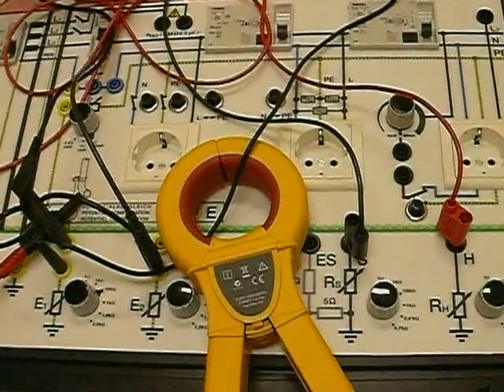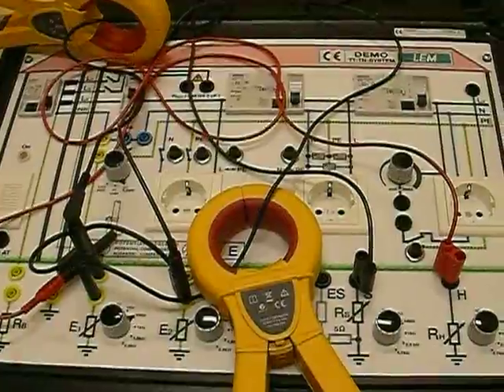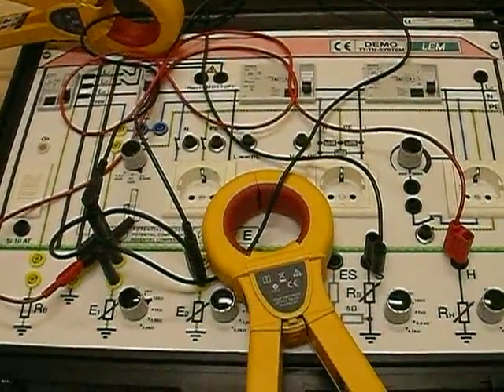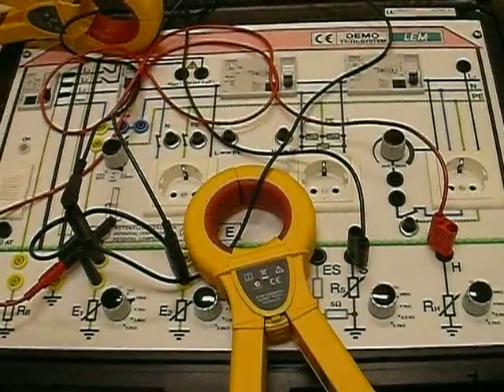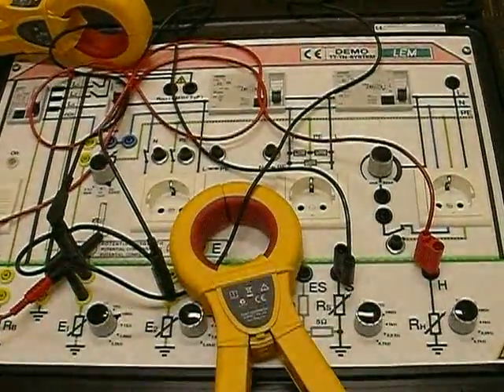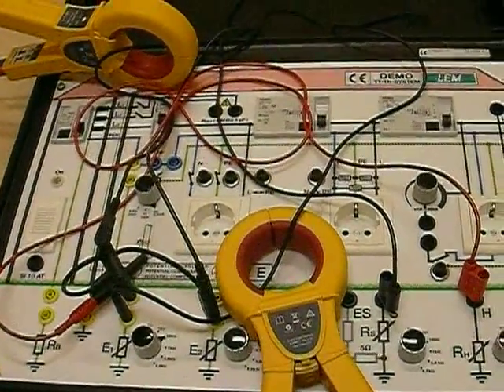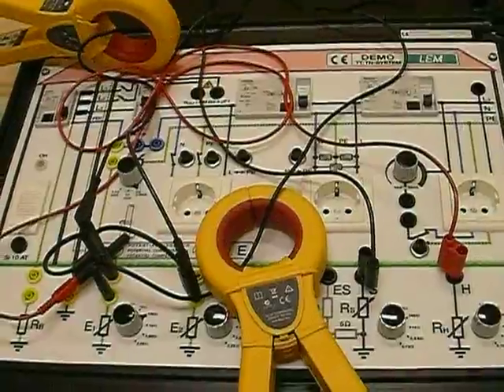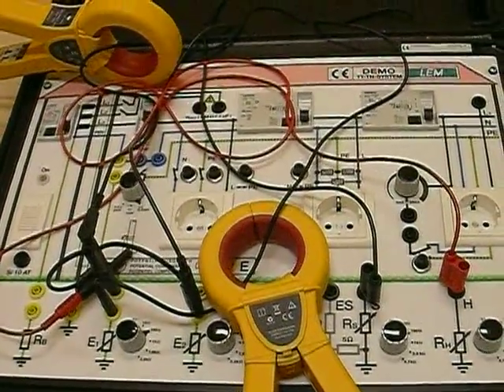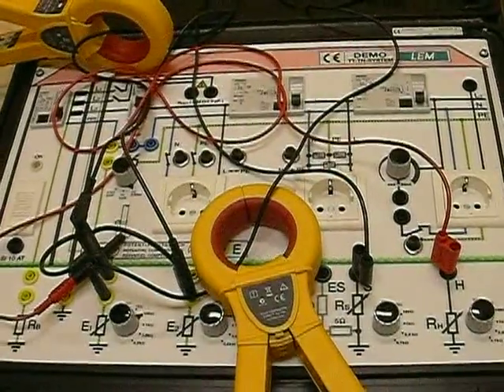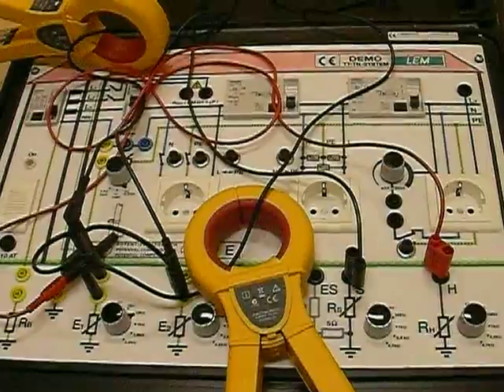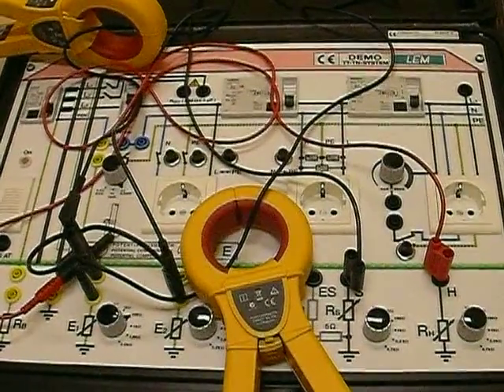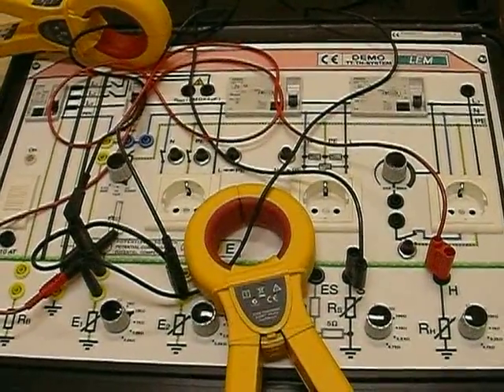So that is the advantage of doing the Stakeless method without having to disconnect the grounding rod or grounding interconnection. There is no need to drive in the stakes RS and RH because in the urban area, there is simply no place for the stakes to be put in for testing. So we conclude the Stakeless method and all the ways that we can test the ground resistance.